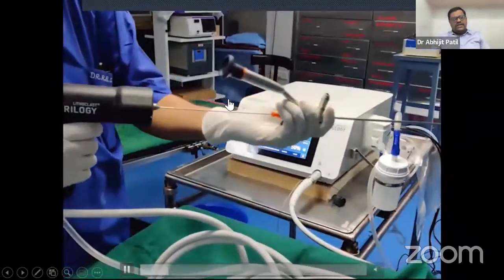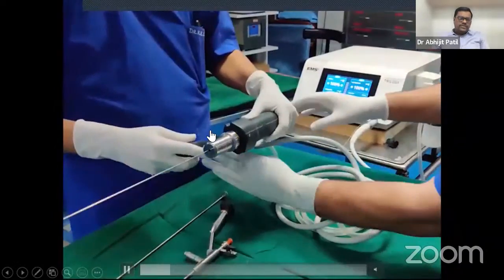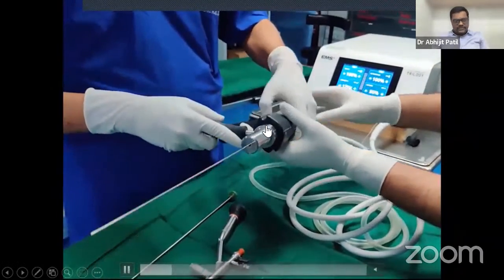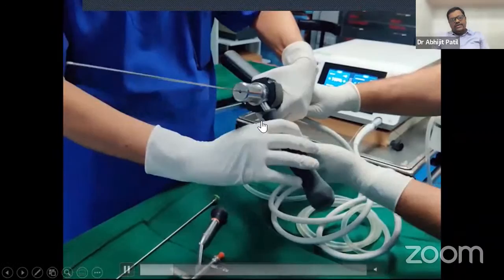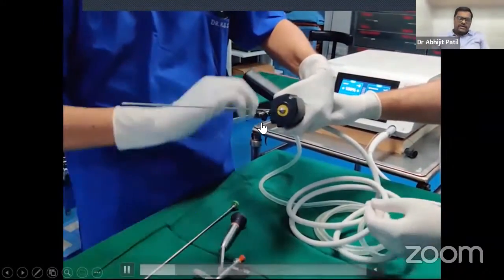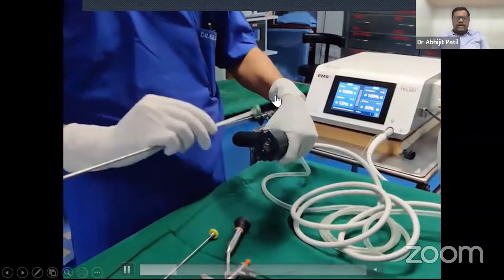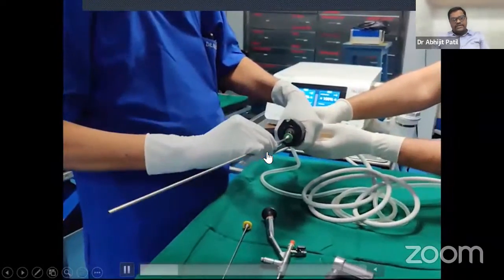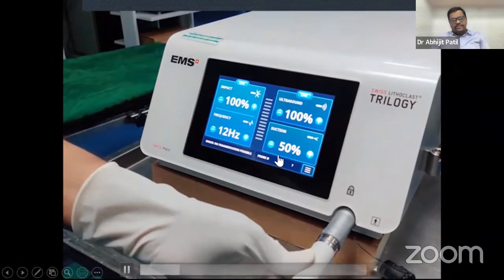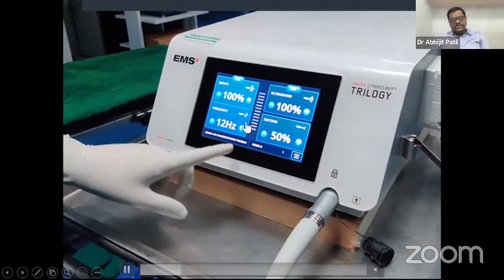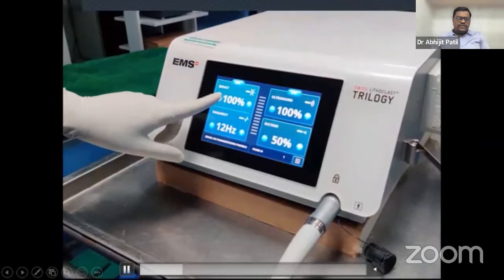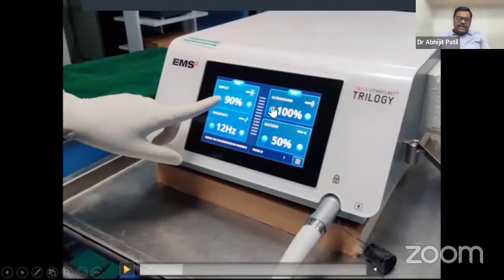Now, this is a 1.9 French probe, which goes through a mini sheath. And if you want to unlock it, use the wrench in anti-clockwise manner, unscrew the probe. And this is a 3.9 French probe, where this can go through a standard PCNL. And this is attached to the machine. Now, these are the three components of it. One is the ultrasound, the intensity of the ultrasound, the frequency of the ultrasound, the impact. This is the ballistic component. And how strong you want the suction. So you can control all the three components in Trilogy.